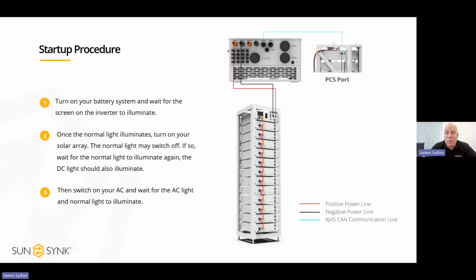Because all of our inverters do work completely off grid. The inverter is happy just being connected to the batteries. So once the battery power is introduced to the inverter, the display on the inverter will turn on. And after a minute or so, the normal light will illuminate above the screen on the inverter.